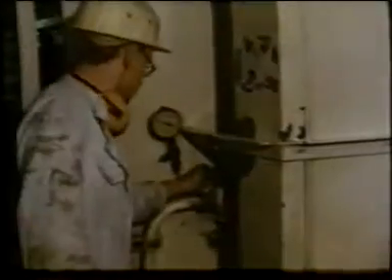Of course, water is the most abundant firefighting medium available at sea, but it obviously has to be pumped to the hydrants. At least 2 main pumps must be available for this purpose, with a third, the emergency fire pump, located away from the engine room in case the main pump should be put out of action or be inaccessible because of fire. The design of a ship's firefighting installation must provide sufficient water for 2 jets to reach any part of the vessel normally accessible to the crew.